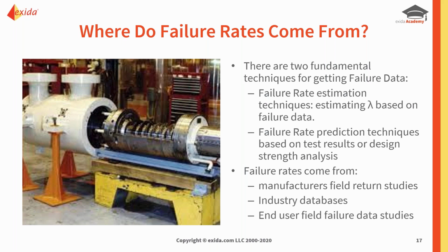So where do we get it from? Well, we can get it from manufacturers, because manufacturers have field return studies. Now, the thing you have to be careful about with manufacturer field return studies, I mentioned this earlier, is that most manufacturers will want to wheedle out the weaker units before they go into population, because they don't want warranty returns.